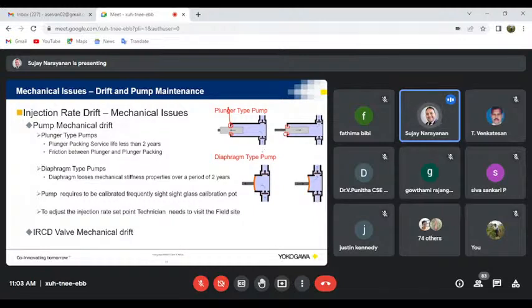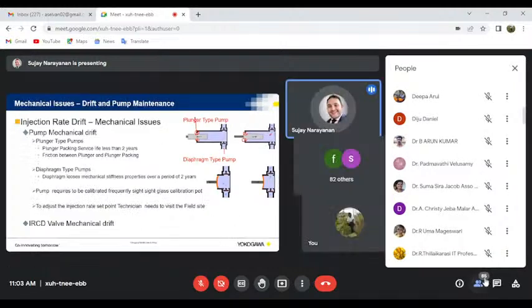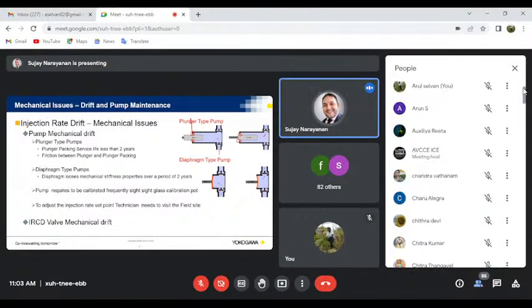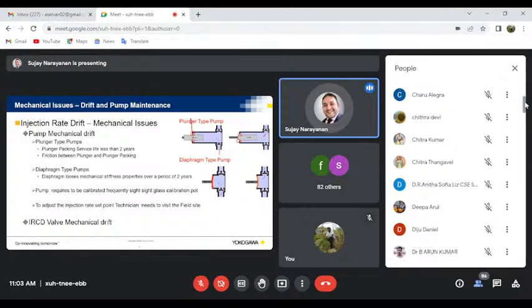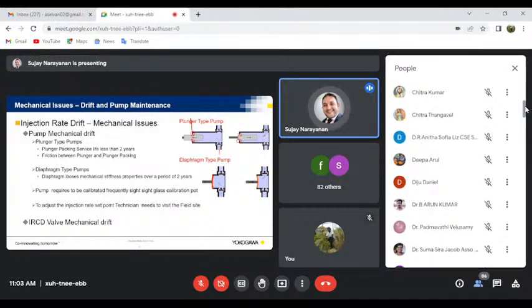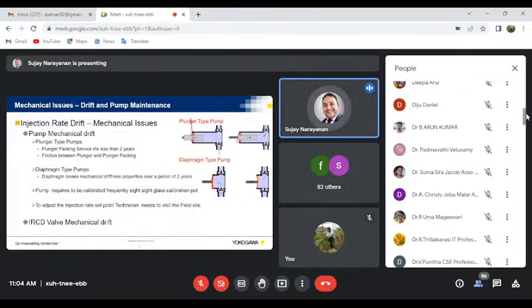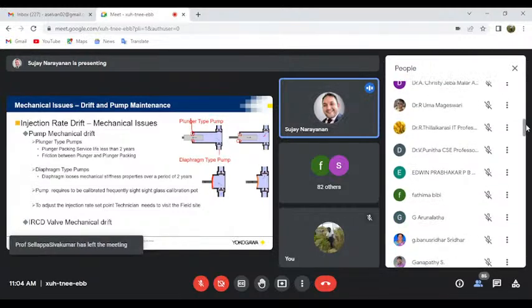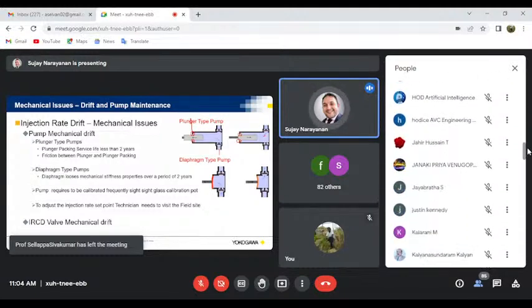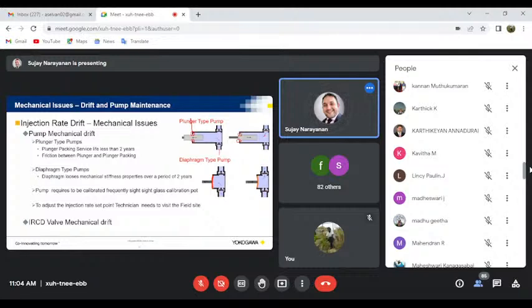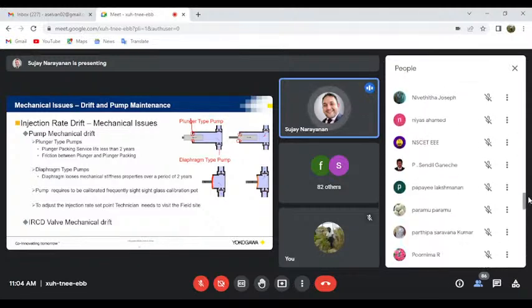It is nothing but sucking the liquid from the suction during the suction stroke, and during the power stroke, it is pushing it up. Now when this seal is compromised, the rate of suction and discharge is also drifting. The same thing happens in the diaphragm type pump. This is an SS316 material diaphragm. Over a period of operation, the elasticity and the stiffness of the SS316 diaphragm is compromised, and that is the reason the drift happens in diaphragm type pumps.